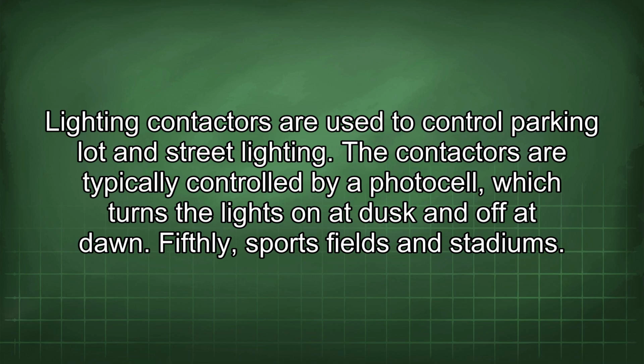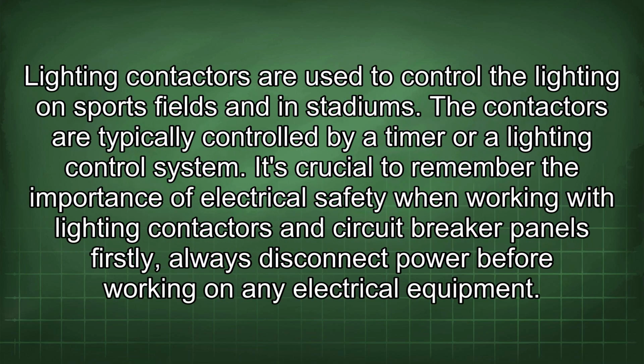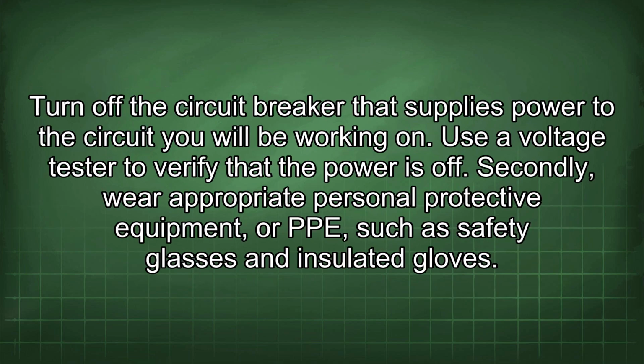Fifthly, sports fields and stadiums. Lighting contactors are used to control the lighting on sports fields and in stadiums. The contactors are typically controlled by a timer or a lighting control system. It's crucial to remember the importance of electrical safety when working with lighting contactors and circuit breaker panels. Firstly, always disconnect power before working on any electrical equipment. Turn off the circuit breaker that supplies power to the circuit you will be working on. Use a voltage tester to verify that the power is off.